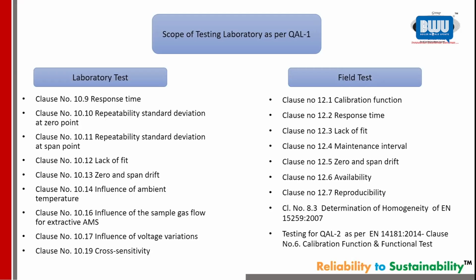There is equipment available, and those who are already in industry know that equipment is installed at the chimney level, including the controller, the gas measurement or dust measurement, including the electronic controller, installed at the chimney level. Now, the entire QAL 1 test of 15267 goes under a controlled temperature between 23 to 28 degrees. Now just tell me, it's not wrong using that. India's tropical condition is that we have from -2 to 49 or 50 degree temperature with 4-5 seasons, different types of humidity, wind and everything. We have different tropical conditions. Now, considering that the tested equipment is at 23 to 28 degrees, if I'm installing that controller at the stack point, you are going to have 100% influence of ambient temperature.